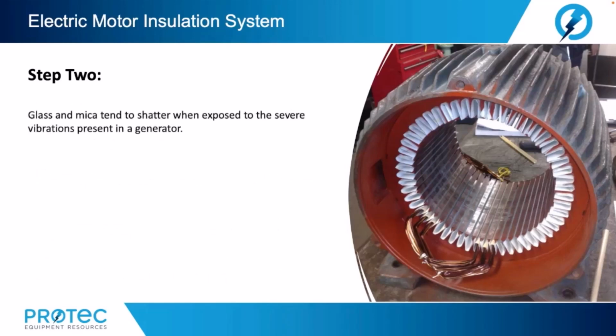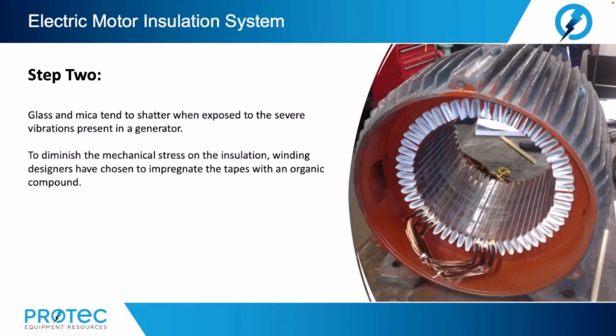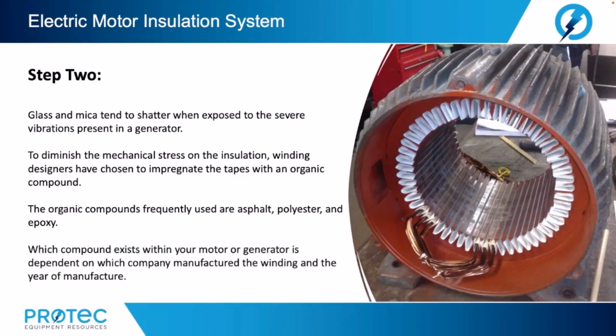Glass and mica tend to shatter when exposed to the severe vibrations presented in a generator. To diminish the mechanical stress on the insulation, winding designers have chosen to impregnate the tapes with an organic compound. The organic compounds frequently used are asphalt, polyester, and epoxy. Which compound exists within the motor or generator is dependent on which company manufactured the windings and the year of manufacture.